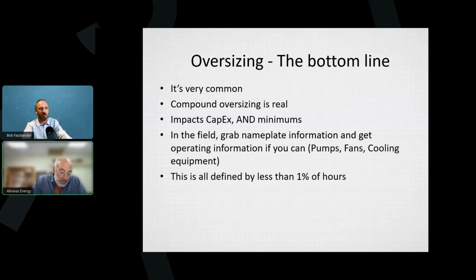Okay, let's say you're a performance contractor. You go to an existing building. You're looking at a pump. The pump's 100 horsepower, and it's constant volume. Let's just say it's a condenser water pump or something. I don't know. Okay, there's an oversizing. Is oversizing going to be a problem here? I mean, I just assume it's 100 horsepower. Are you replacing the pump? No, I don't want to replace the pump.